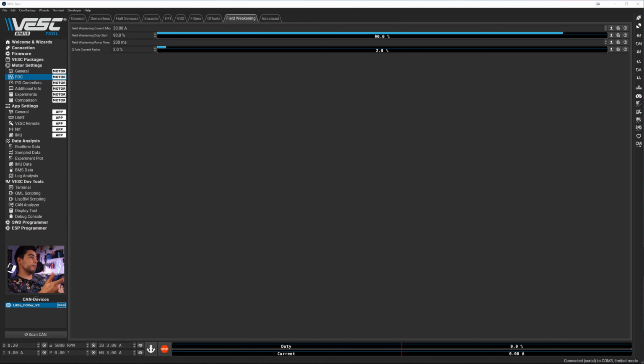For the rest of the field weakening settings, you want to have the duty start at around 65%. This is where it starts as the zero point to start ramping in the field weakening effect. Let's see if the field has any info. Not really, so just set it to 65. He says don't go lower than 60, otherwise it'll start causing issues. You probably could even go a little higher, but we'll just set it to 65.